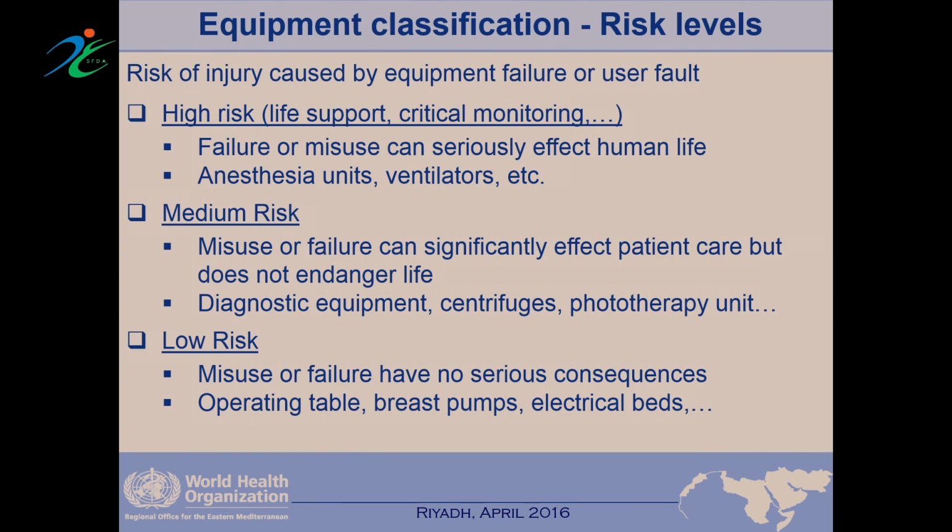To start from scratch, they need to go step by step. Maybe at the first level, consider the high-risk equipment, to ensure that whatever high-risk equipment is available in your hospital or your country is monitored and captured in your database, and that you are able to ensure its functionality, at least to minimize any risk to the patient from using that equipment.